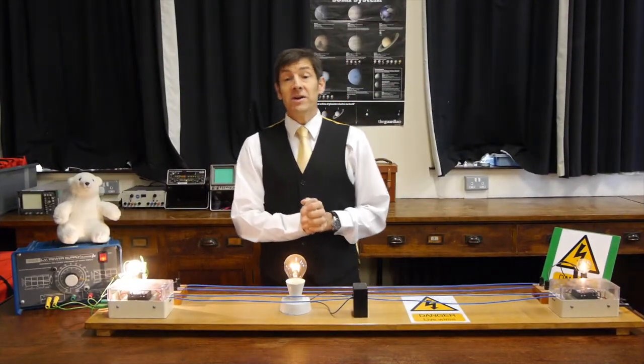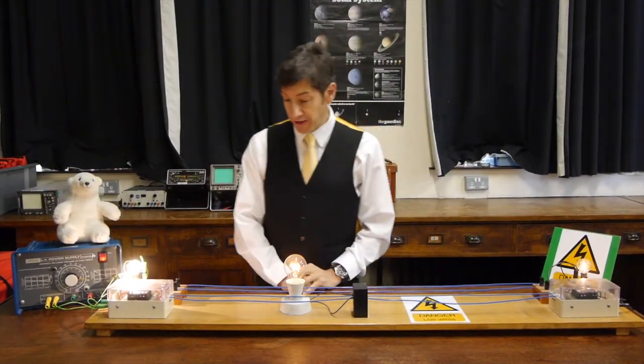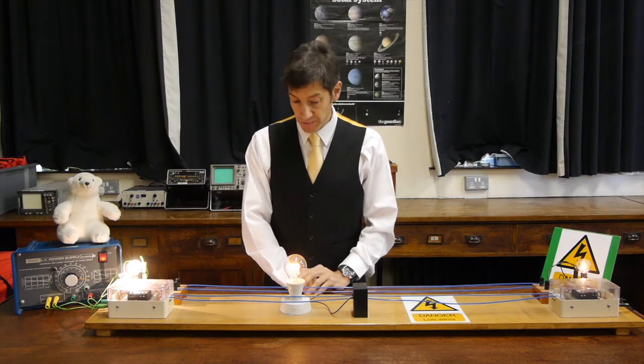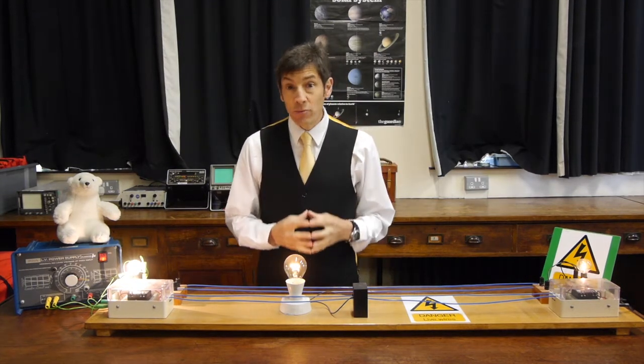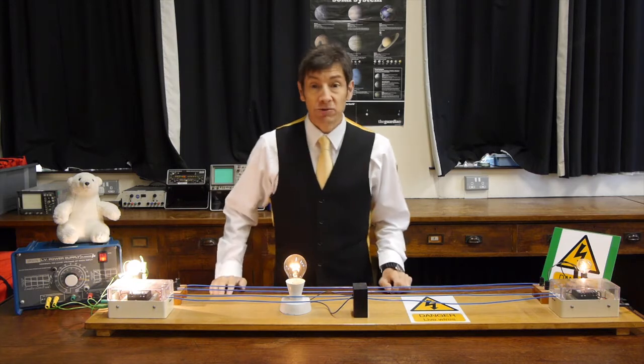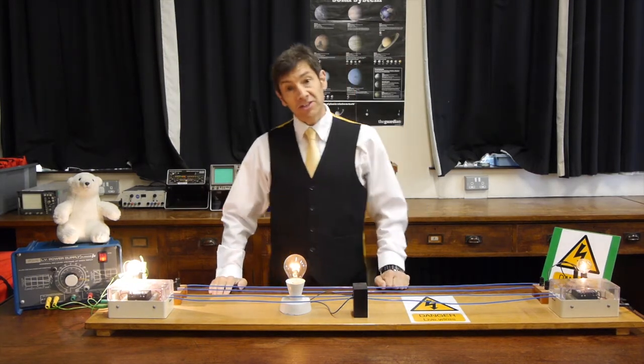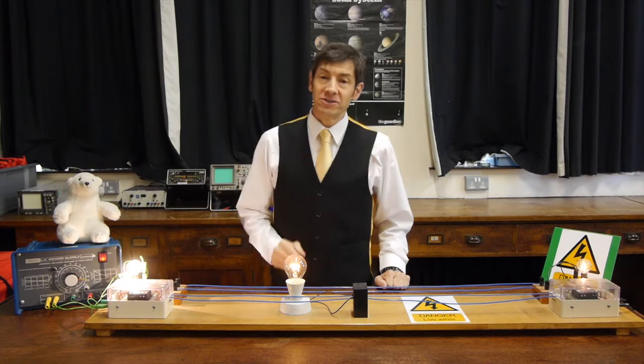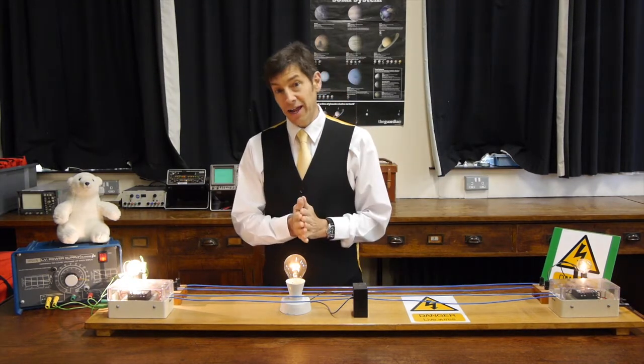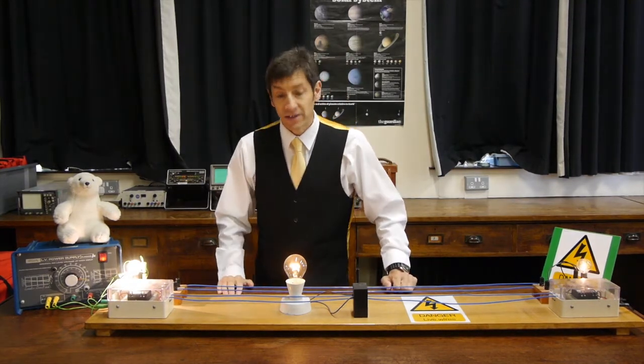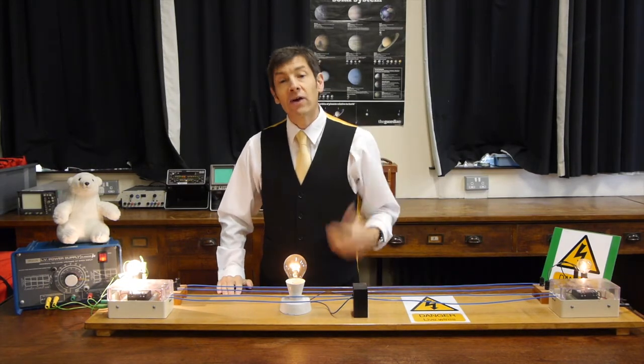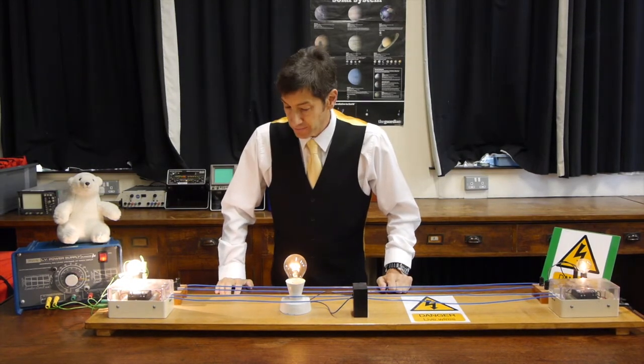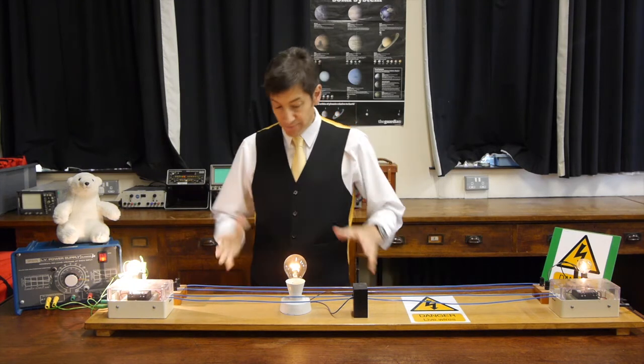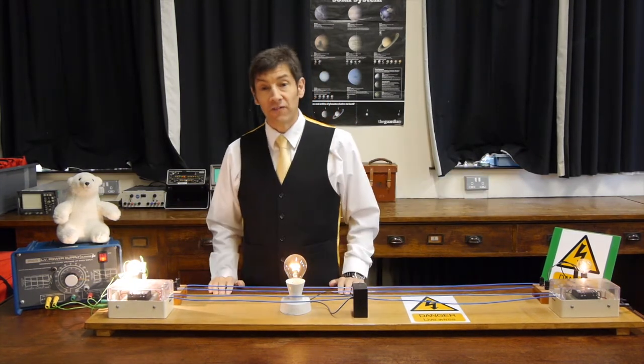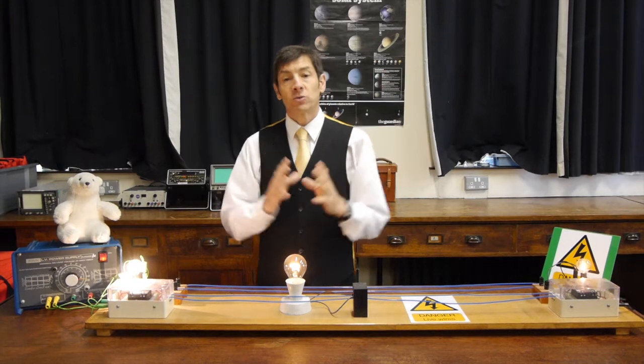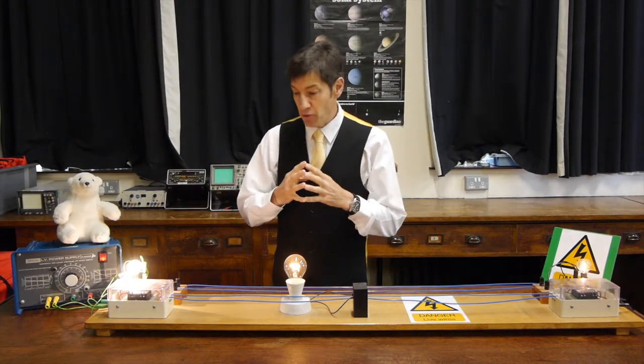Current is not a good thing in national grid cables. Current causes ohmic heating because the cables have resistance. It's a good thing in a toaster - you pass a lot of current through the elements in a toaster or hairdryer and they glow bright red, giving out energy as heat. But we don't want to heat up the cows, sheep, and horses in the fields under the national grid, so we keep the current really low.